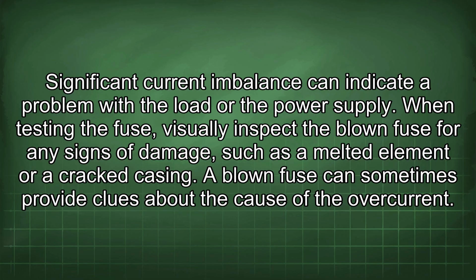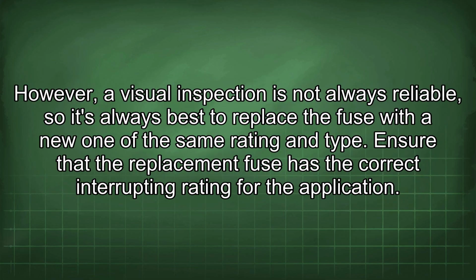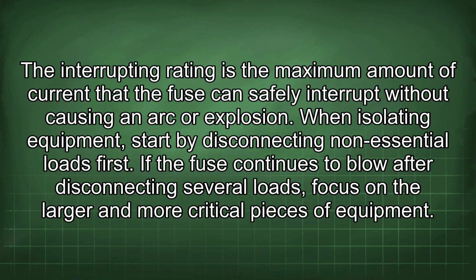When testing the fuse, visually inspect the blown fuse for any signs of damage, such as a melted element or a cracked casing. A blown fuse can sometimes provide clues about the cause of the overcurrent. However, a visual inspection is not always reliable, so it's always best to replace the fuse with a new one of the same rating and type. Ensure that the replacement fuse has the correct interrupting rating for the application. The interrupting rating is the maximum amount of current that the fuse can safely interrupt without causing an arc or explosion.